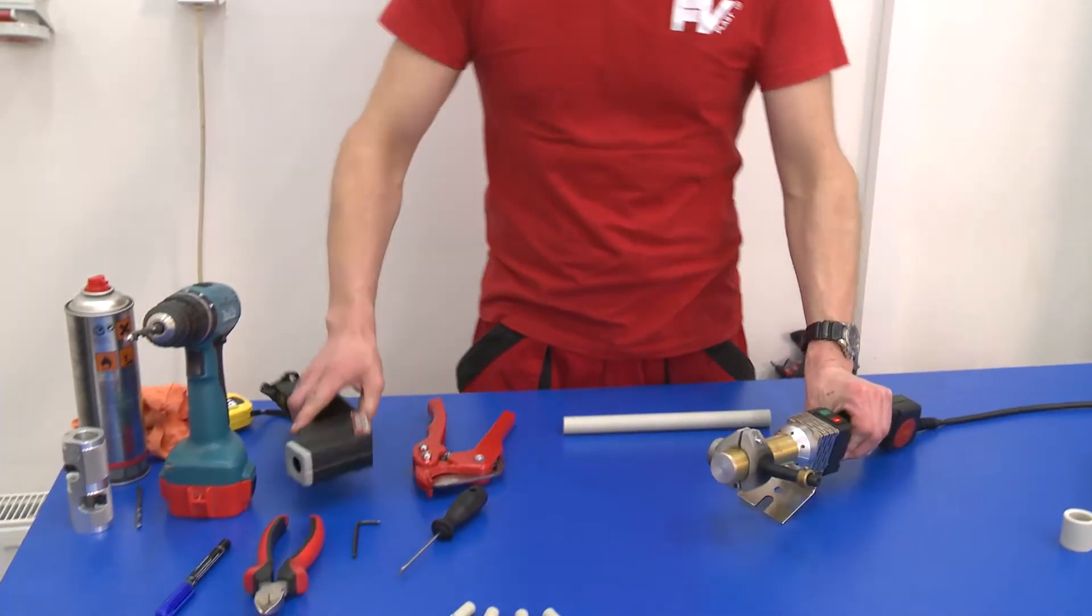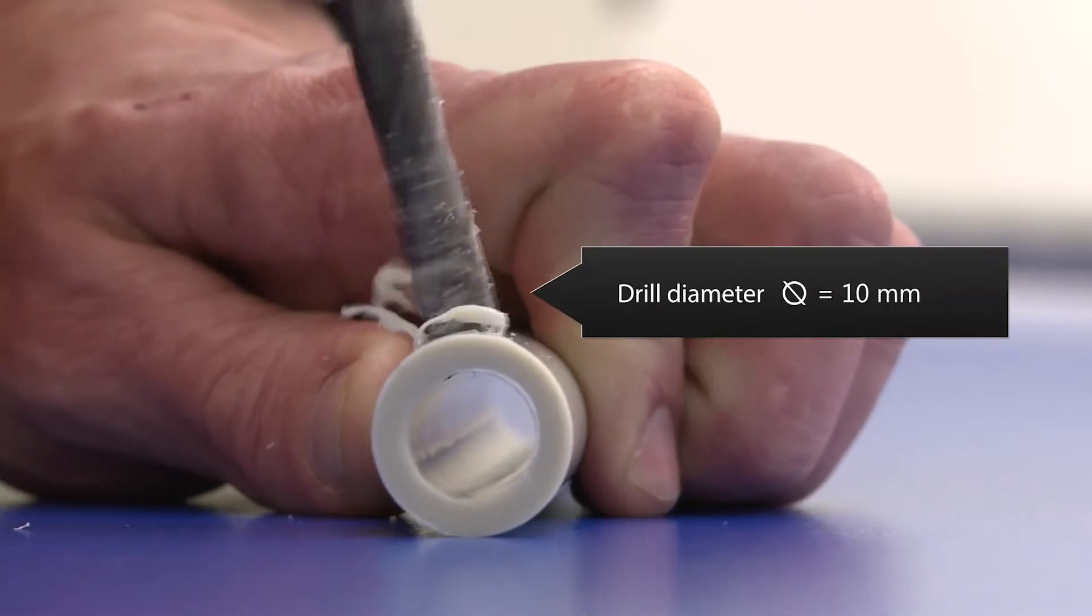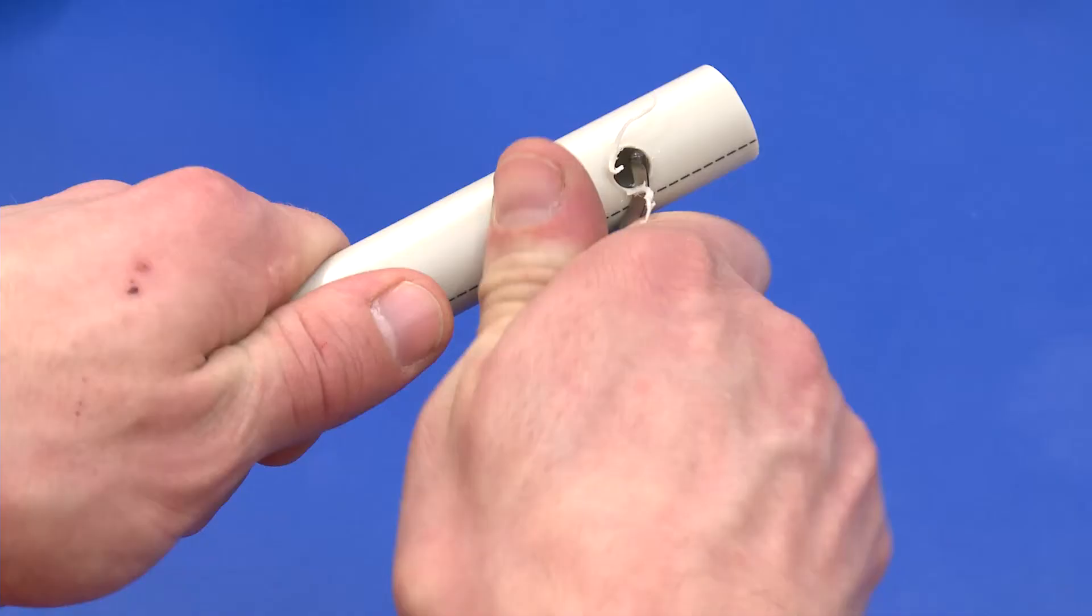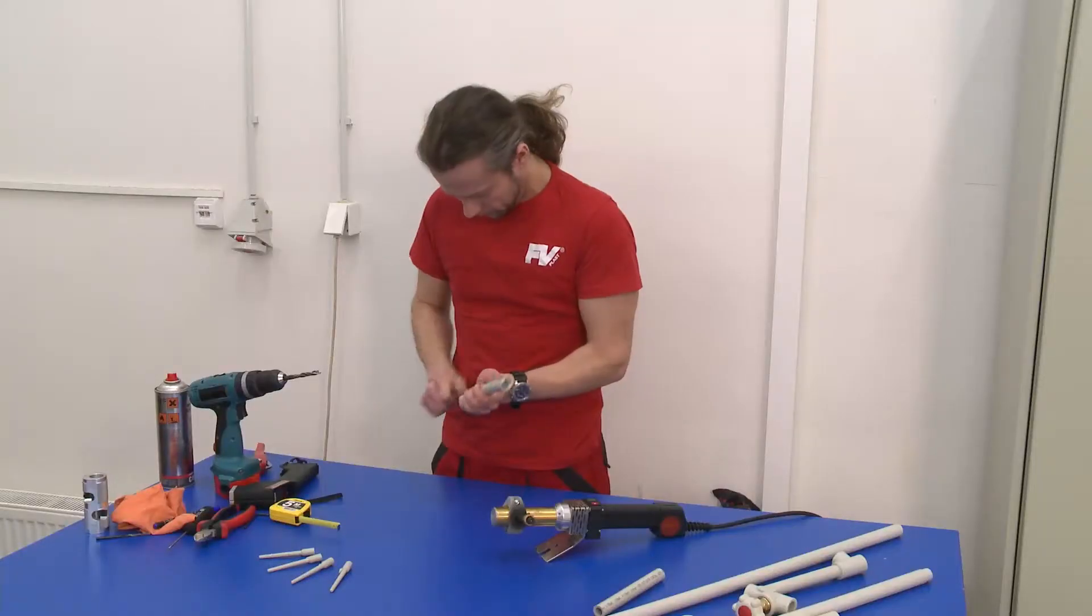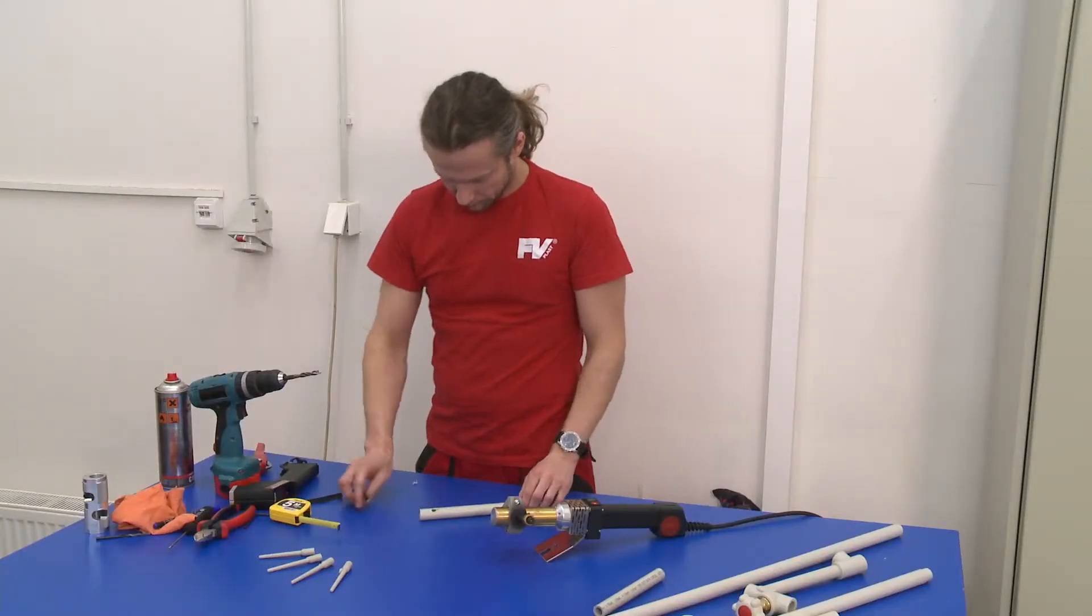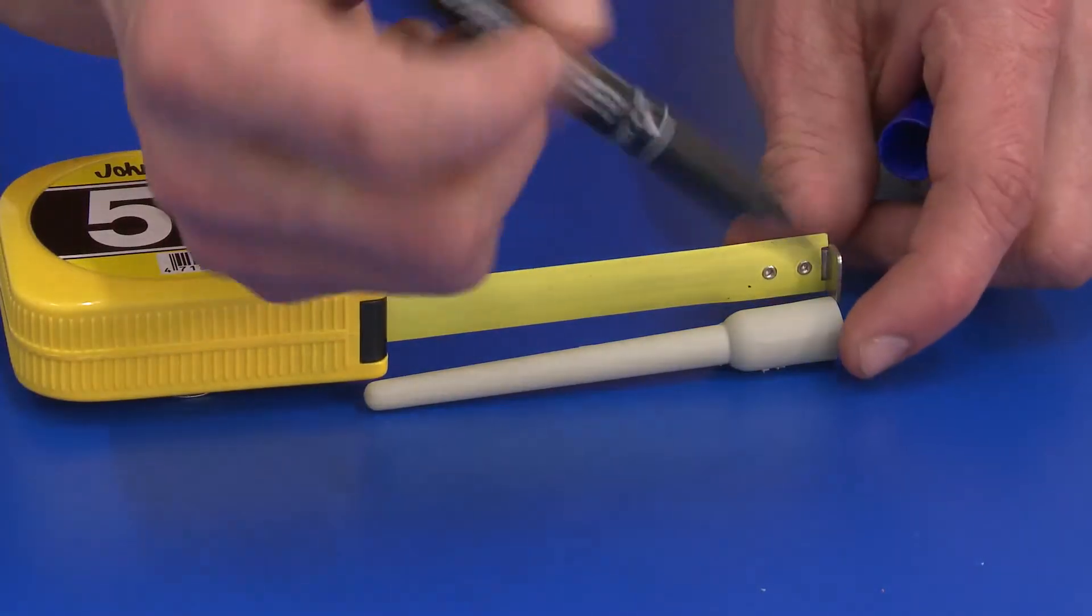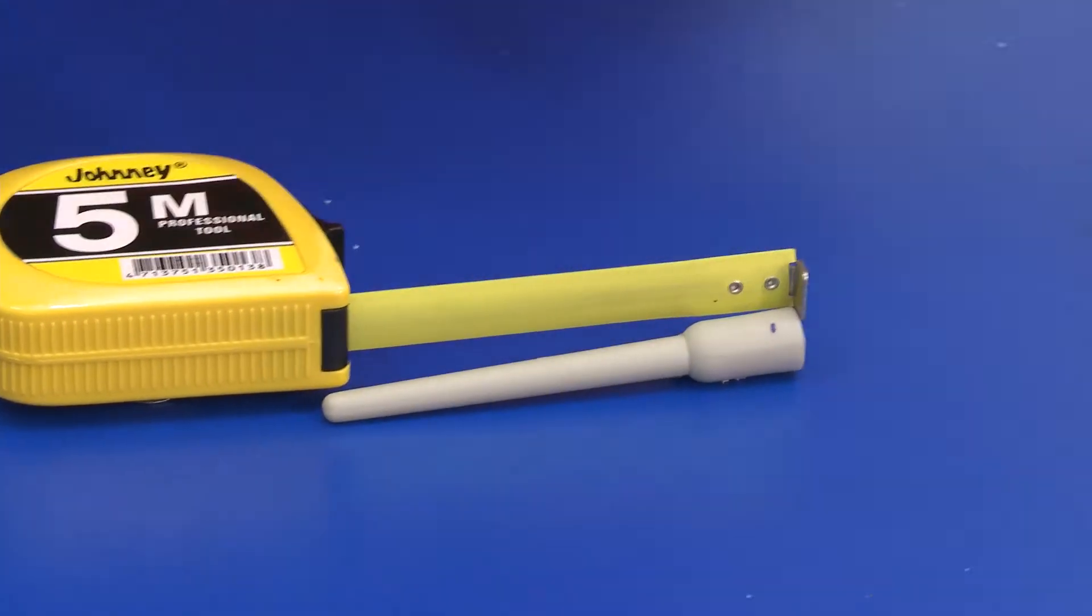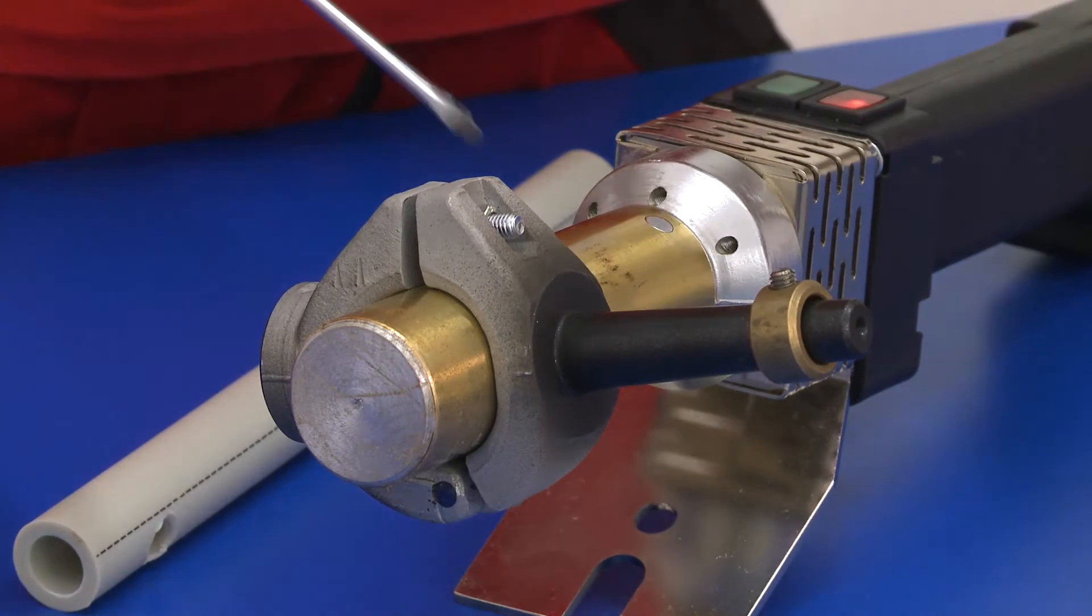The hole must be re-bored using a drill with a diameter of 10 millimeters. The calibrated hole is cleaned of burr and for the stubby tube we strive to eliminate the aluminium layer in the vicinity of the weld. On the corrective mandrel we measure and indicate insertion depth according to the thickness of the repaired pipe. We also set the spacer ring.